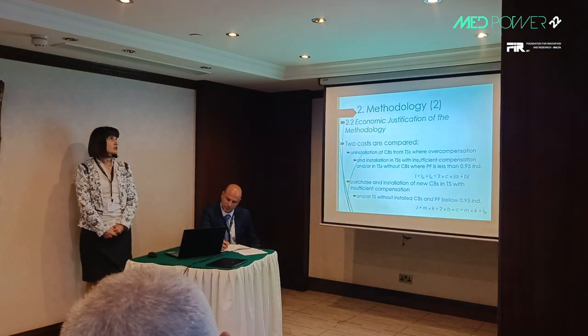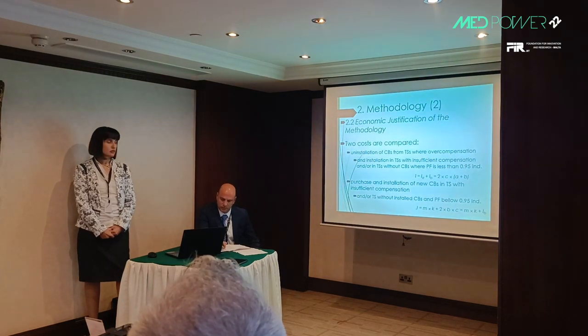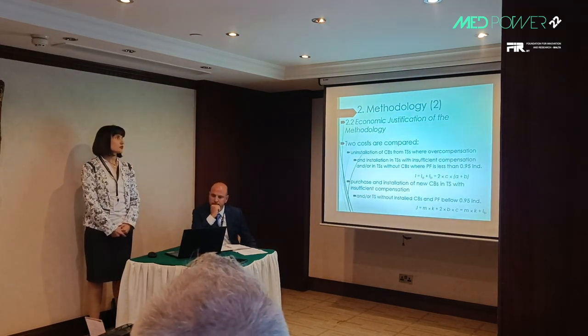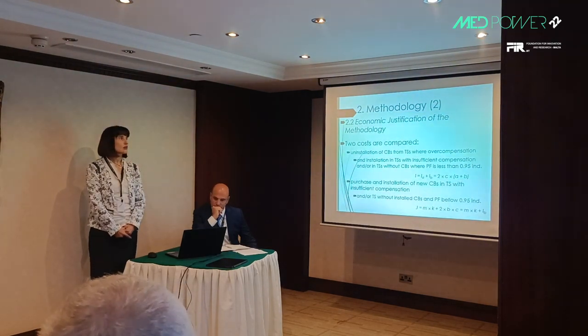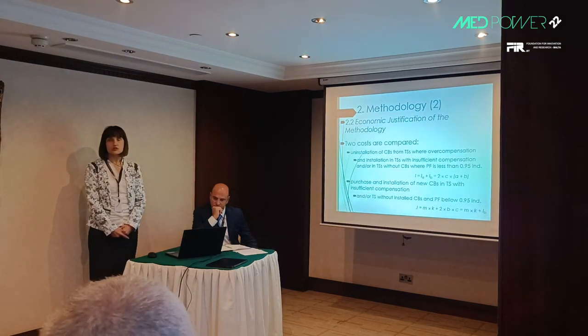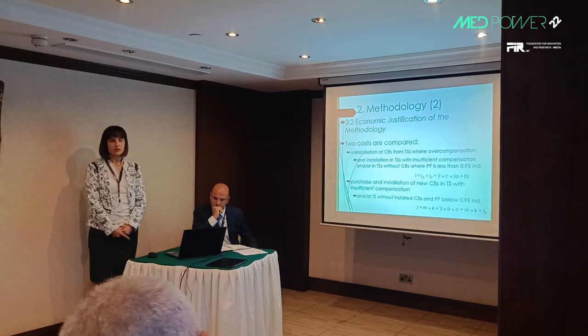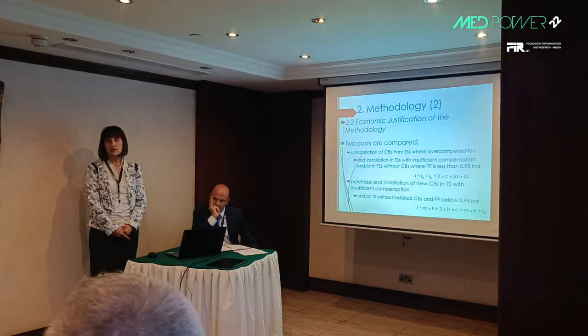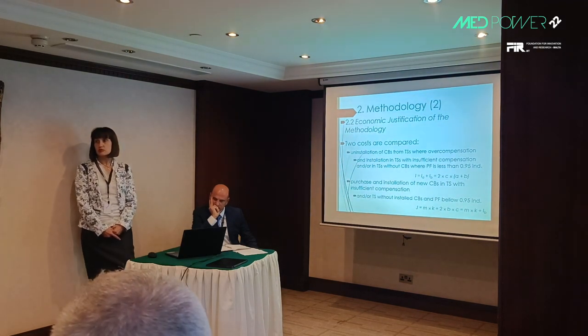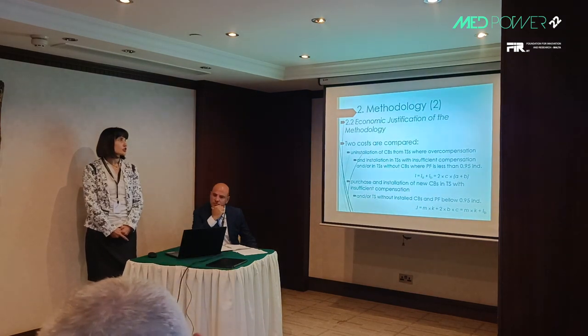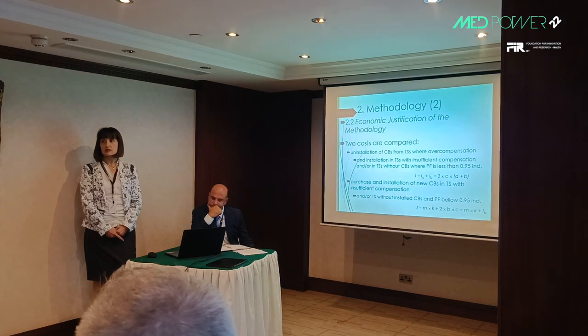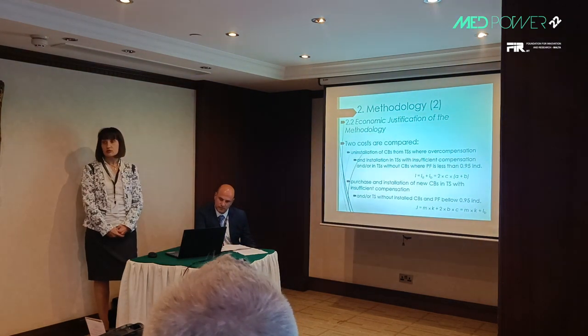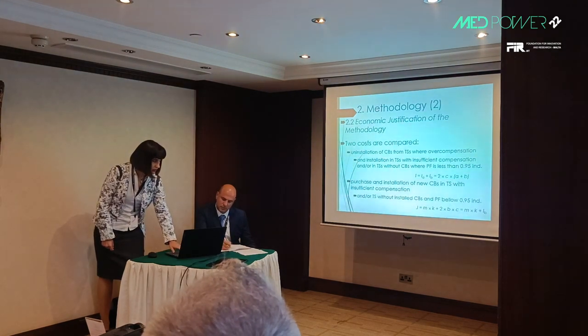The methodology is also economically justified. Two costs are calculated and compared to each other. The first is the cost of uninstalling capacitor banks from transformer substations where overcompensation is noticed, and installing them in transformer substations without capacitor banks and low power factor, or in transformer substations which have capacitor banks but where insufficient compensation is noticed.